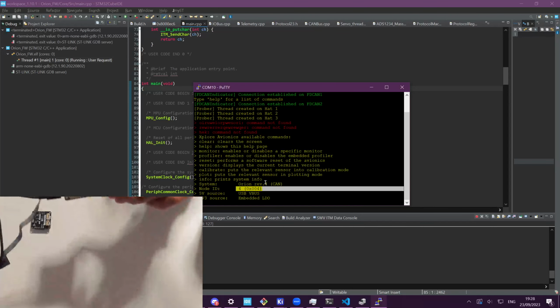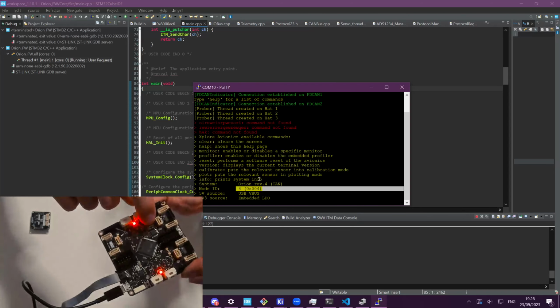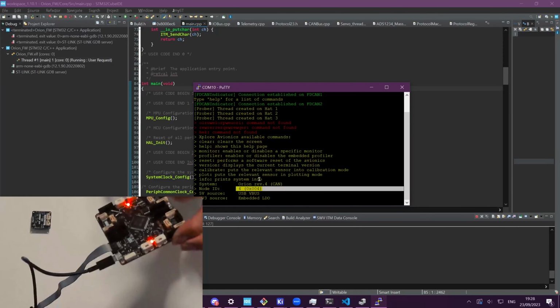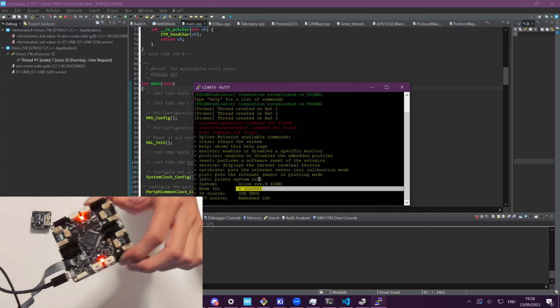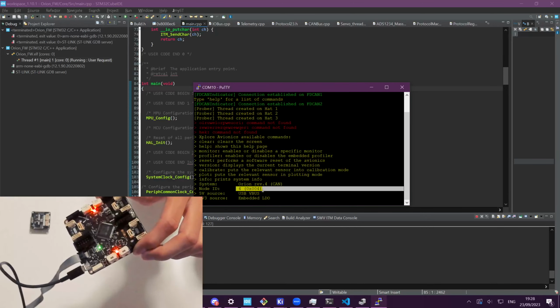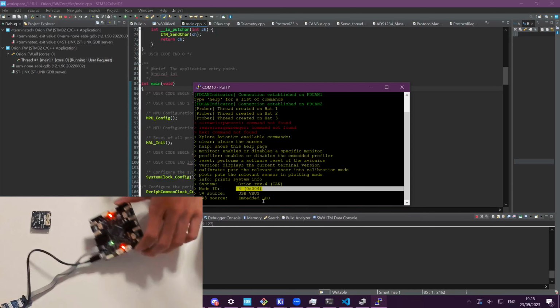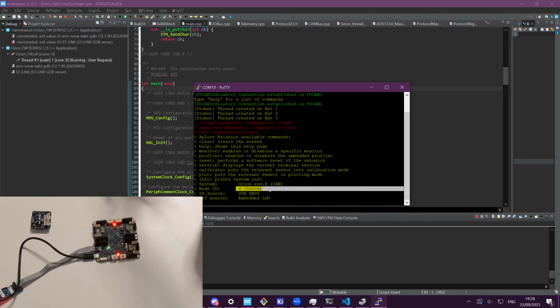If you look at the node ID here, you can see that one of the dip switches is on, and it is actually the third dip switch. If you do 2 to the power of 2, it's equal to 4. Because the first dip switch is at index 0, the second one at index 1, and the third one at index 2. So this is the correct ID that we have.